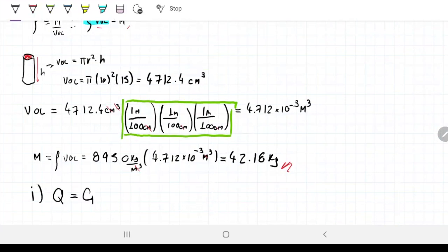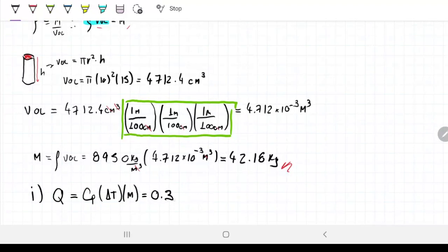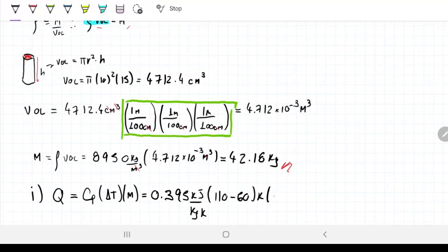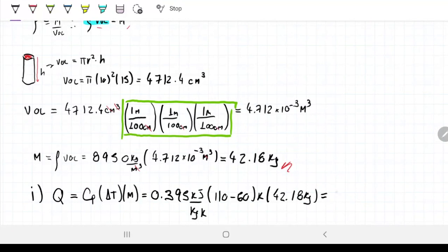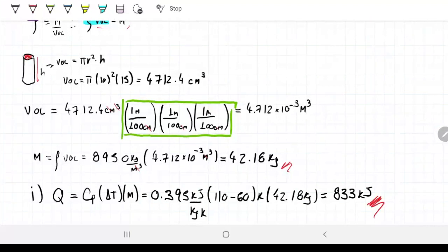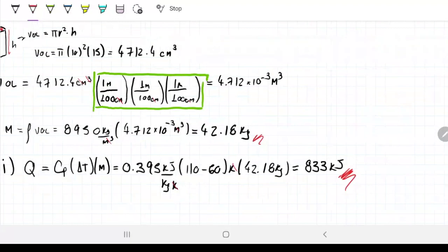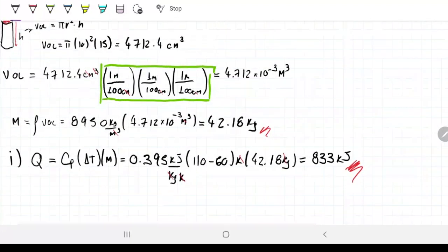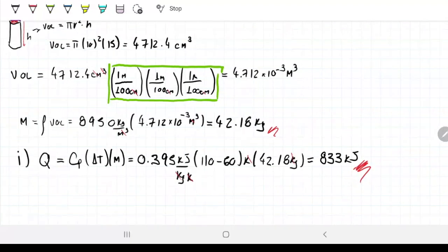...that's the easiest part. The energy needed is Q = m × Cp × ΔT. In our case: Cp = 0.395, ΔT = 110 − 60 = 50 kelvin or Celsius, and mass = 42.18 kg. That gives us 833 kilojoules. So that's the amount of energy needed to raise the temperature of this cylinder from 60 to 110°C.